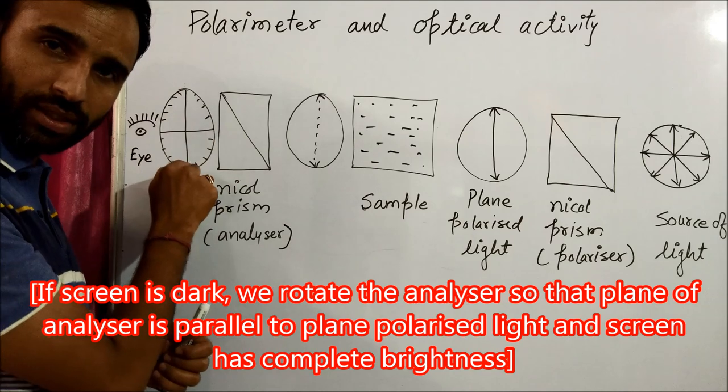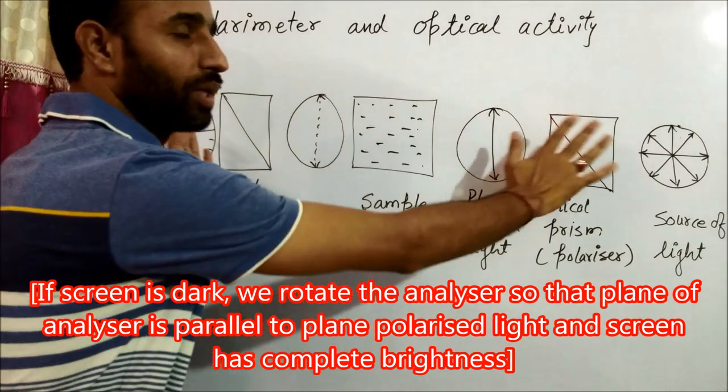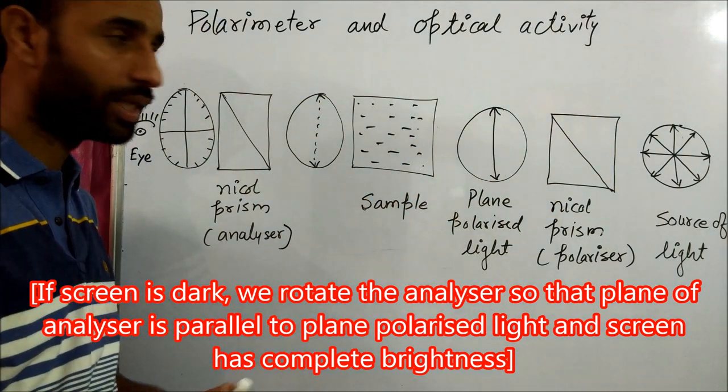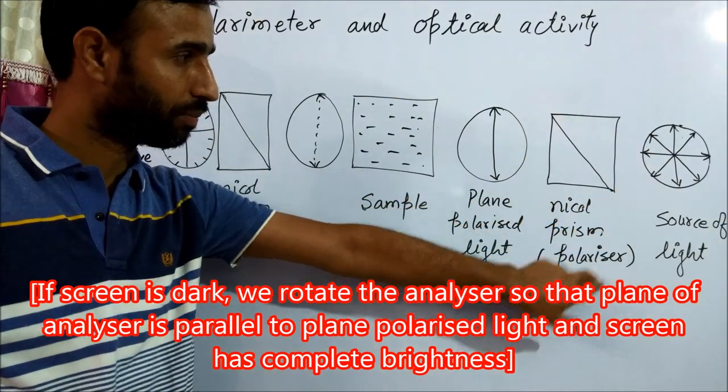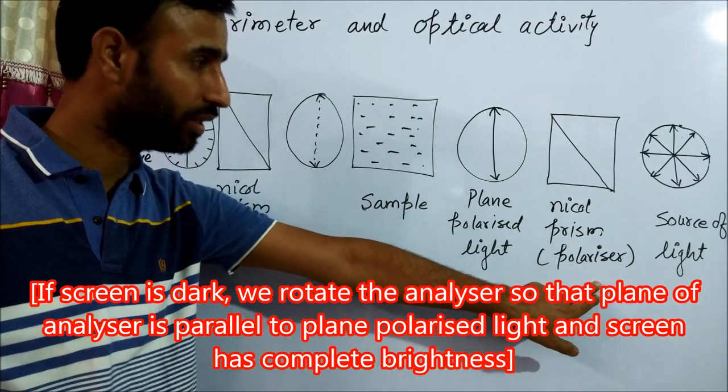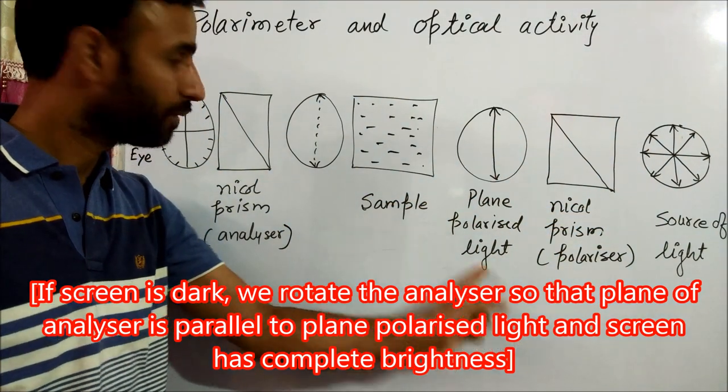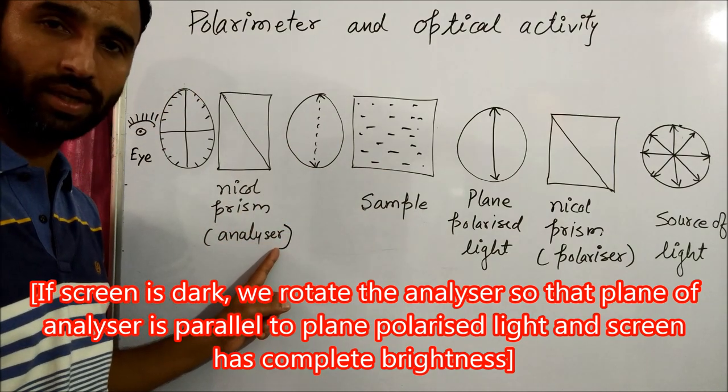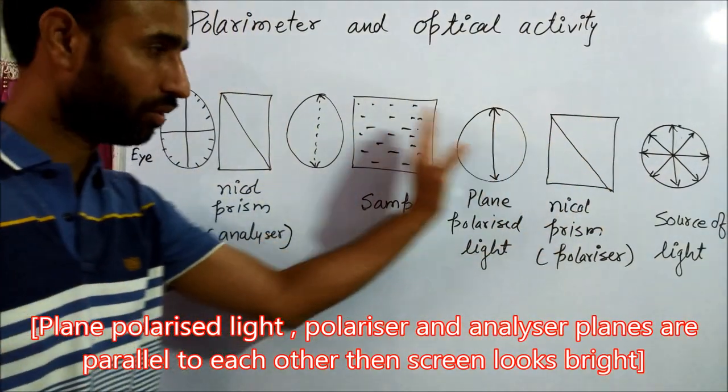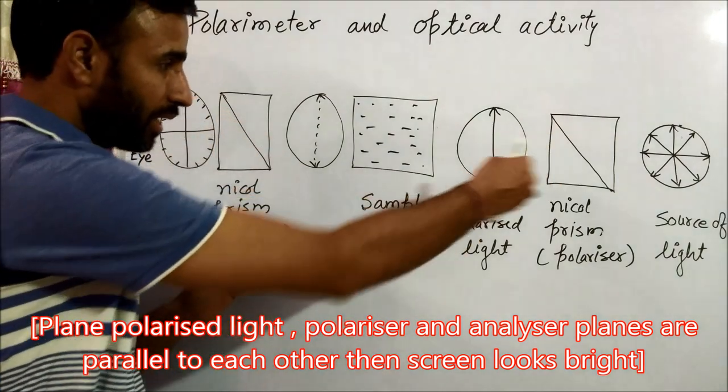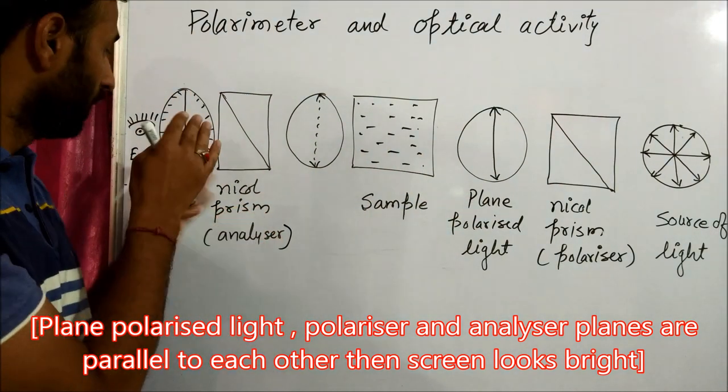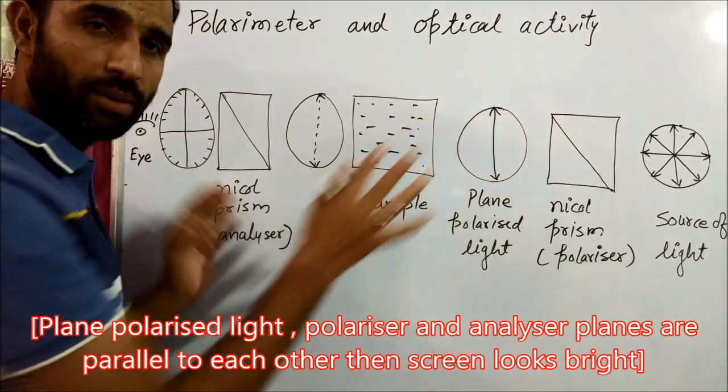It is complete brightness, that means our instrument is calibrated. That means the plane of this nicol prism polarizer plane to the light plane and analyzer plane, they are parallel to each other. All are parallel. That is why light can pass through it. So now the instrument is calibrated.